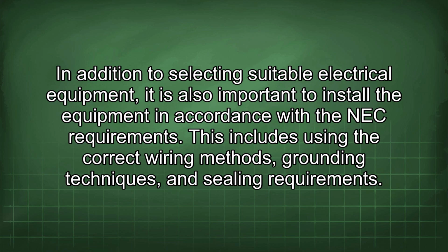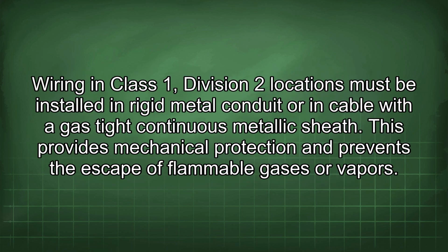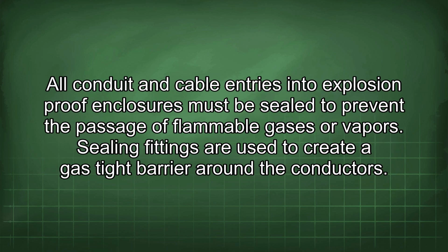In addition to selecting suitable electrical equipment, it is also important to install the equipment in accordance with the NEC requirements. This includes using the correct wiring methods, grounding techniques, and sealing requirements. Wiring in Class 1, Division 2 locations must be installed in rigid metal conduit or in cable with a gas-tight continuous metallic sheath. This provides mechanical protection and prevents the escape of flammable gases or vapors. All conduit and cable entries into explosion-proof enclosures must be sealed to prevent the passage of flammable gases or vapors. Sealing fittings are used to create a gas-tight barrier around the conductors.